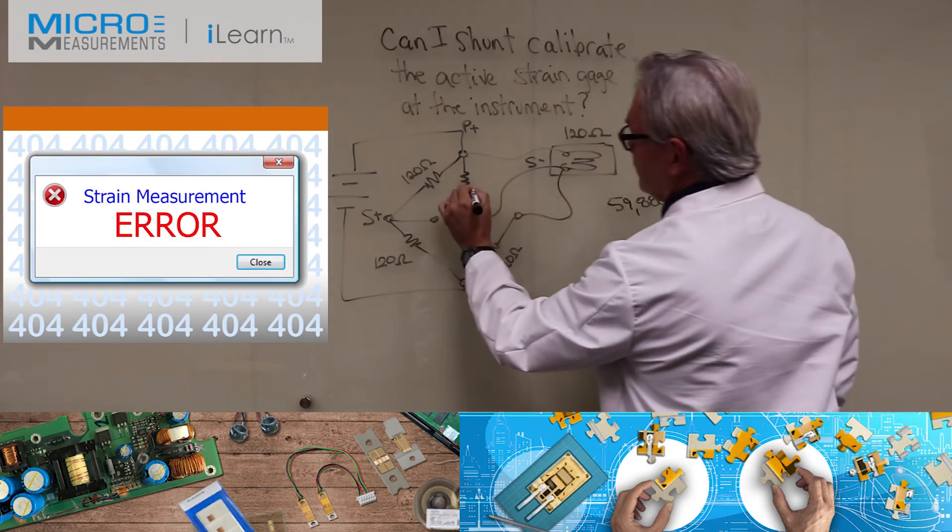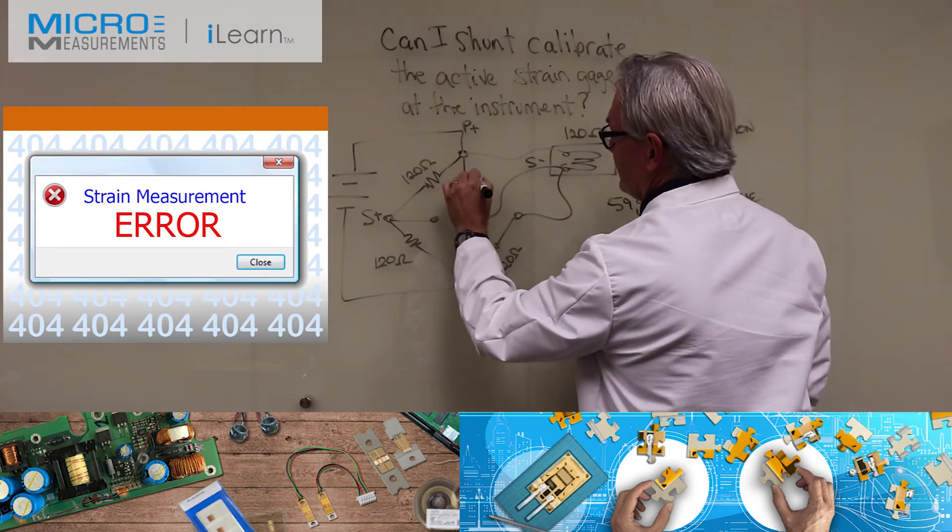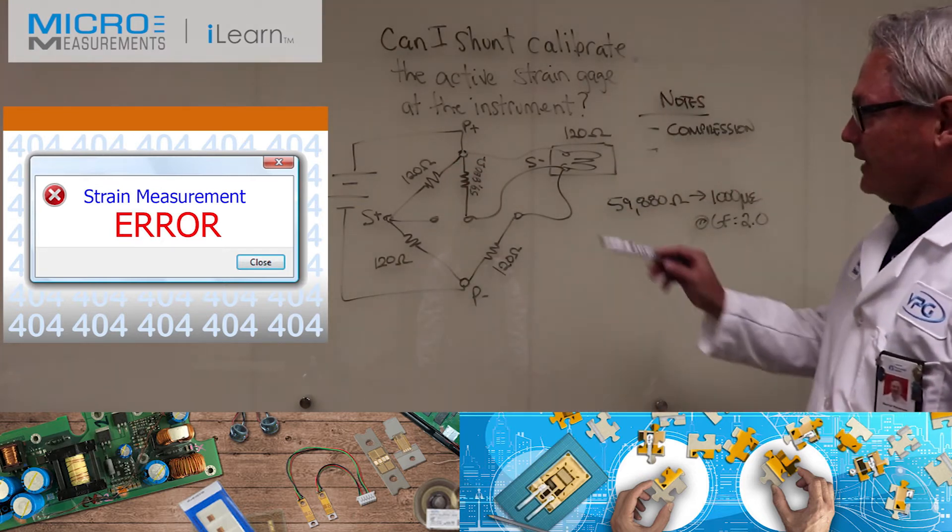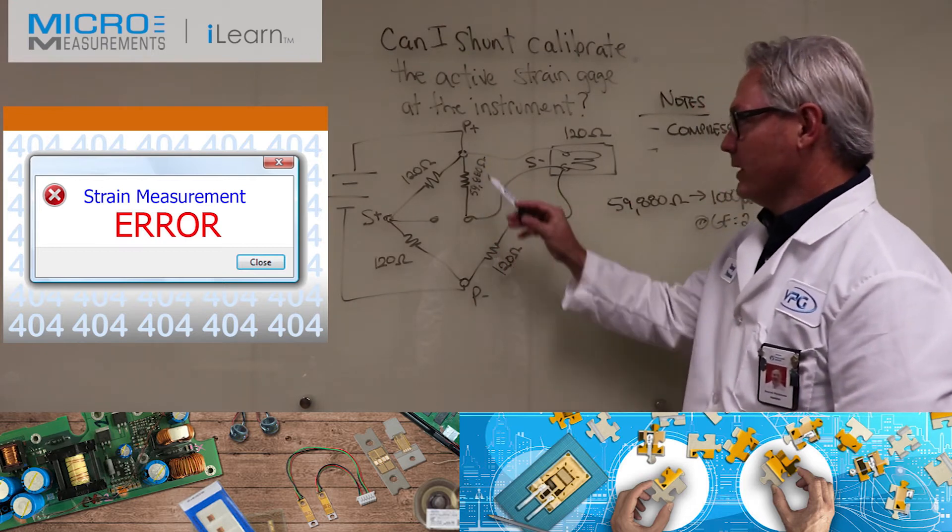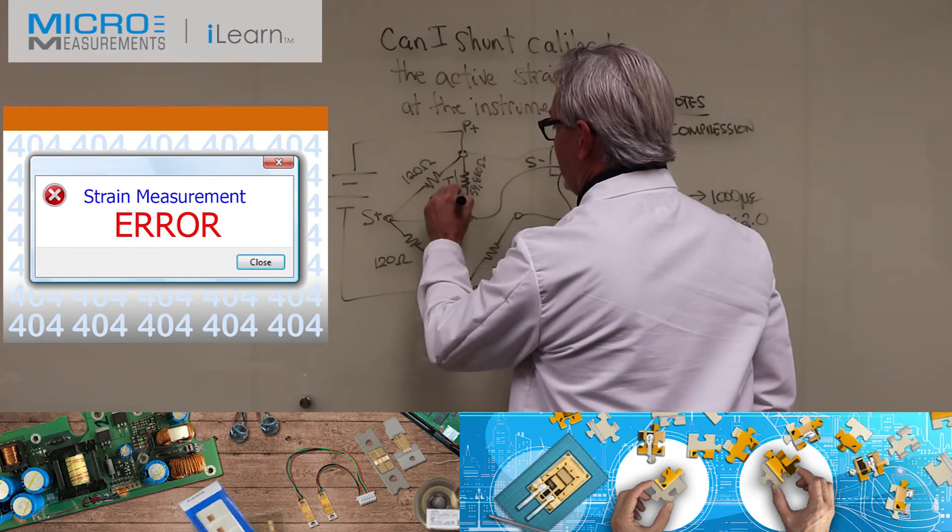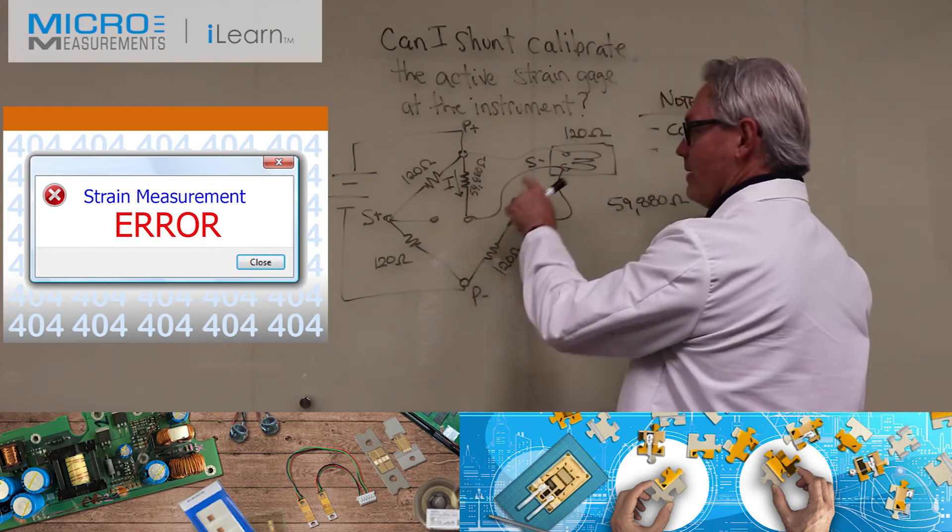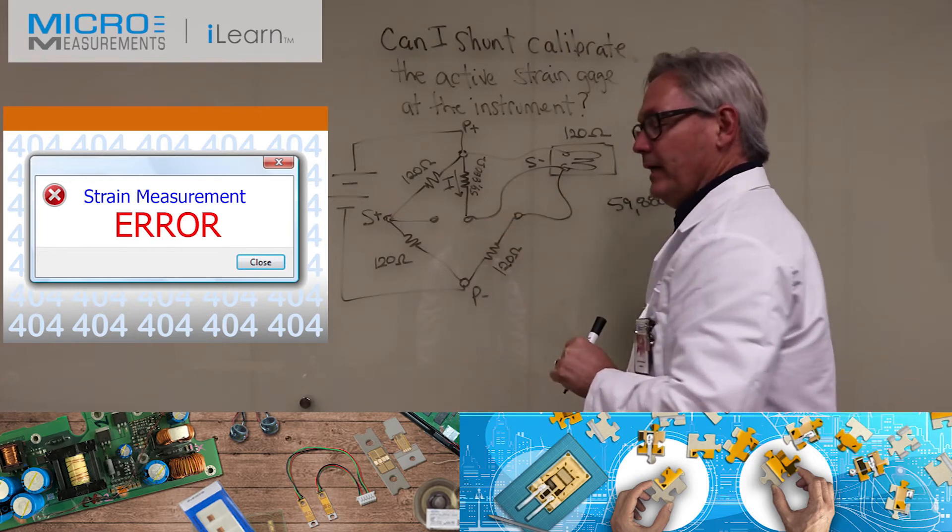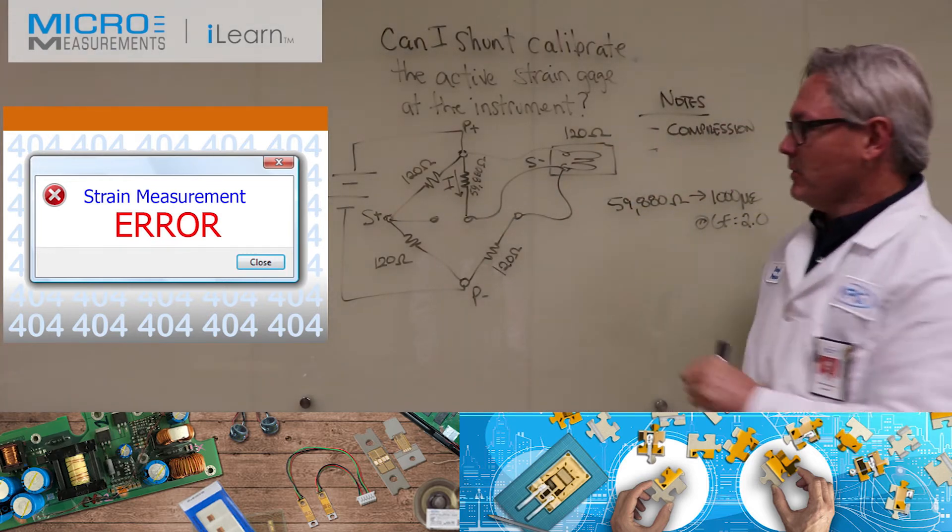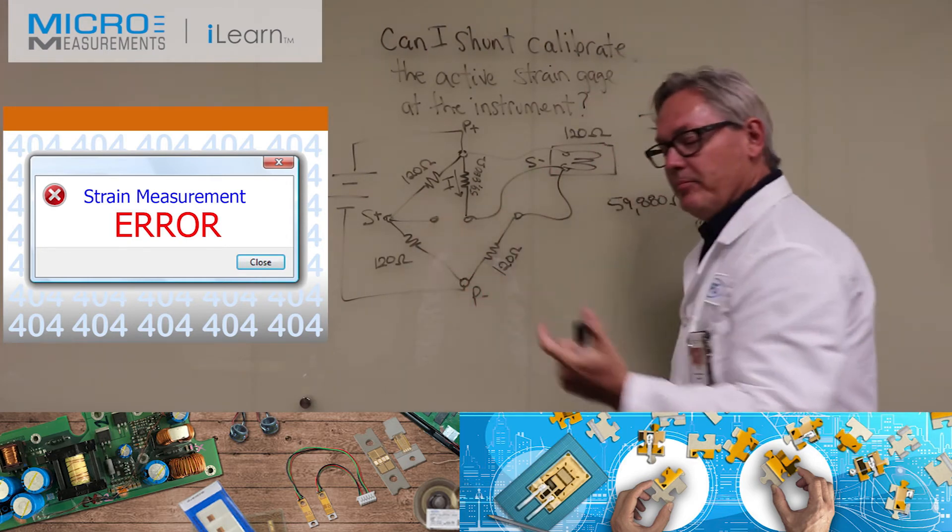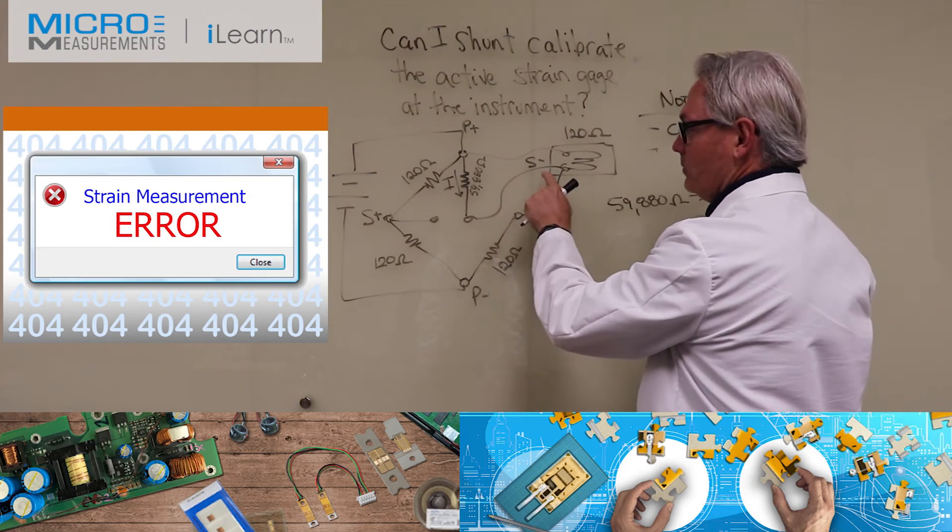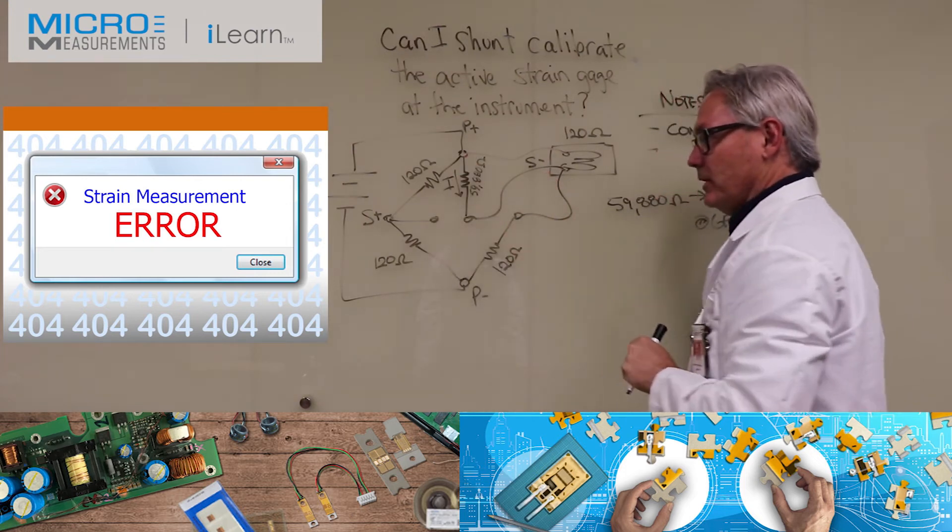Commonly we like to use 59,880 ohms because that will produce a thousand microstrain simulation at a gauge factor equal to 2.0, assuming you've got a 120 ohm strain gauge. So if I connected at this spot, one of the things you've got to realize is that you start drawing a current through that resistor and you drop it onto this signal wire.